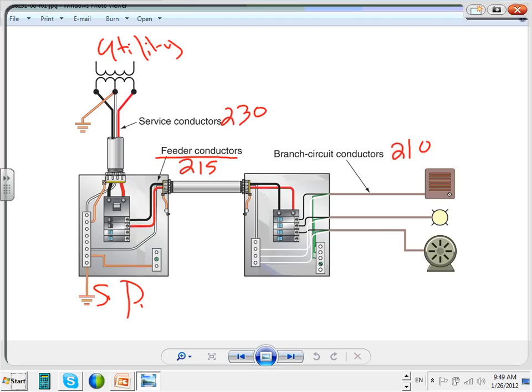Any question, guys, about this layout? The reason why I like this picture is because it clearly defines, if I'm looking for conductors for the service, which article in the NEC code book should I go to? 230, 215, and 210. Any questions about this? So just a quick reminder, when we were doing branch circuits, your branch circuits most of the time have a 20 amp. Commercially, you're probably using 20 amp, 30 amp, 40 amp, 50 amp, up to 60 amps. Very common.